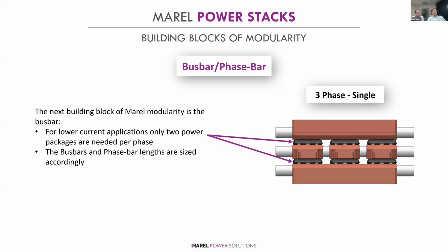Going back to those building blocks of modularity, I said the bus bar and the phase bar are a big part of that. The sizing of your overall package is determined by the current requirements. So here we see what we call a three-phase single — it's only two power packages of these Trident power packages per phase, one per switch. And the bus bar lengths are sized accordingly.